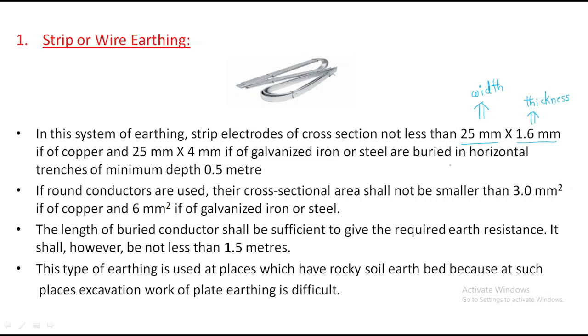1.6 mm is the thickness. So this length depends on the material. If it is copper, this is for the copper; we have to use this metal. And 25 mm by 4 mm for galvanized iron. If galvanized iron is used, these calculations must be used. Or steel, galvanized iron or steel, both are the same. They are buried in horizontal trenches at a minimum depth of 0.5 meter from the ground. If it is ground, we have to use this buried into the 0.5 meters length. Yes.